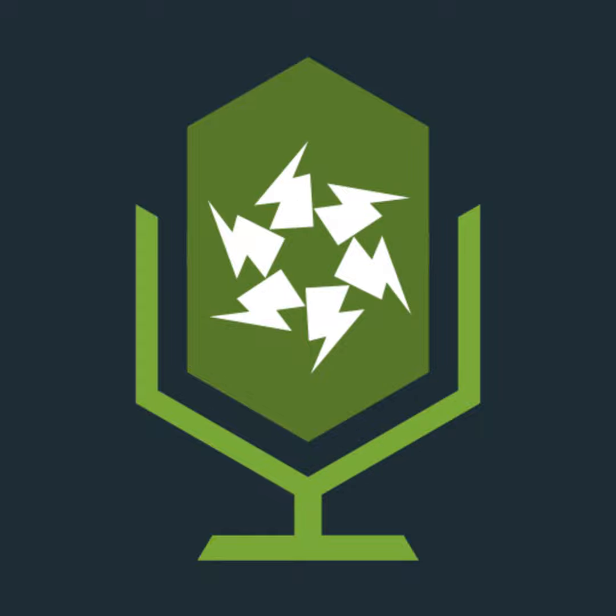When we come to fuses though, like this 3036, there are varying amounts of current required to achieve varying disconnection times. So I need to calculate a current for 0.4 seconds, but I also need to calculate a current for 5 seconds, and I have to put them both into a table back in part 4. Well, they've done that. So if I go back to part 4, to where those tables were, in chapter 41, one of them is table 41.2, and the other one is table 41.4.